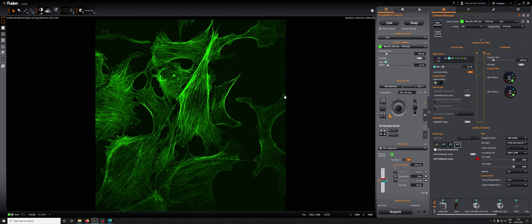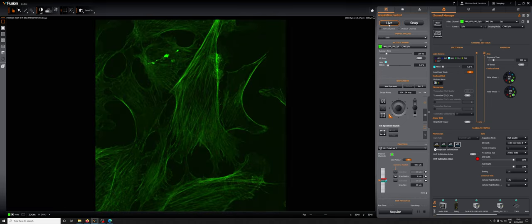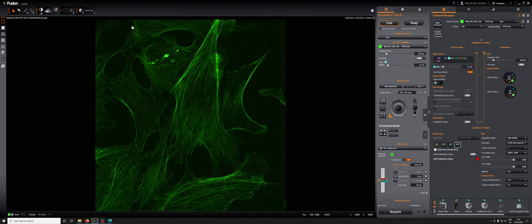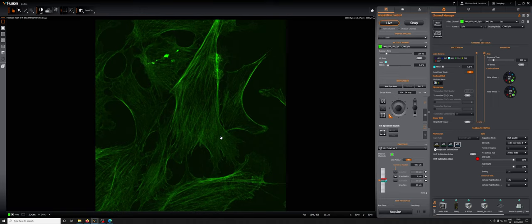The field of view will be smaller and my signal to noise will be smaller as well. So if I go to live you can see that all those things are true. We have a smaller field of view, a smaller pixel size so we're able to discern a little bit more detail, and the image looks noisier because there's less light going to each pixel because the light from the sample is spread out more.